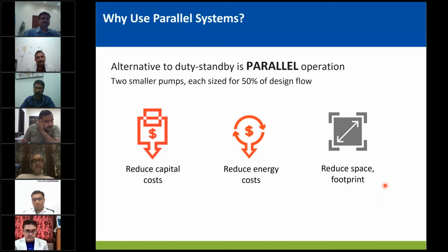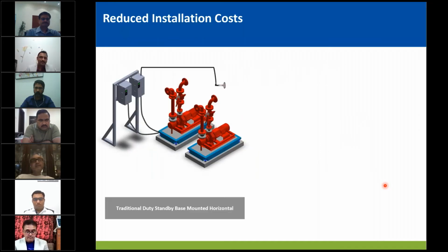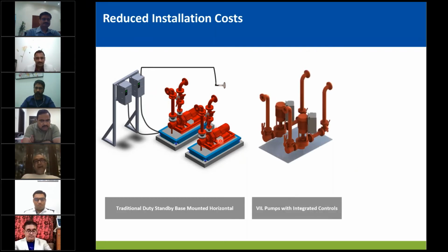In parallel, two smaller pumps, each sized for 50% design flow, can reduce capital cost, reduce energy cost, and reduce space footprint. So if you look at the traditional way of installing pumps that we have been practicing for many years: two horizontal pumps with inertia bases, flex connectors, variable speed drives on the rack or in the panel, and the DP sensor installed in the pipes and wired back to the controller or variable speed drive. Now, look at the footprint of this, the space occupied not just by the pumps, but also by the control panel, etc., and the serviceable space required around the pumps.